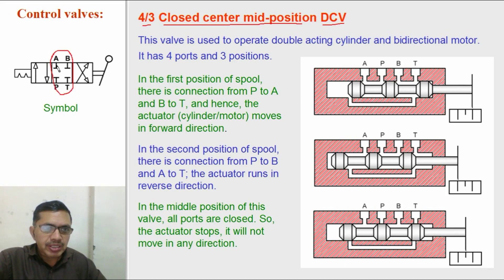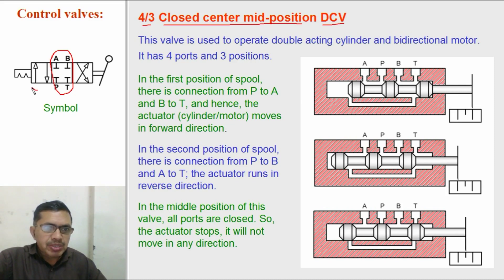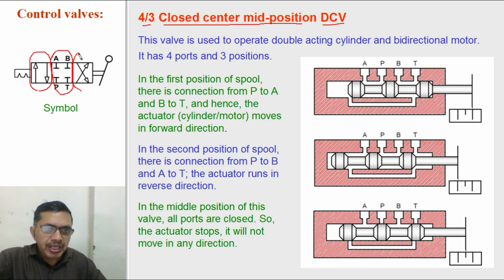In this middle position A, B, and T are all closed. In the first position there is connection from P to A and B to T. In the second position there is connection from P to B and A to T, and in the middle position all ports are closed.